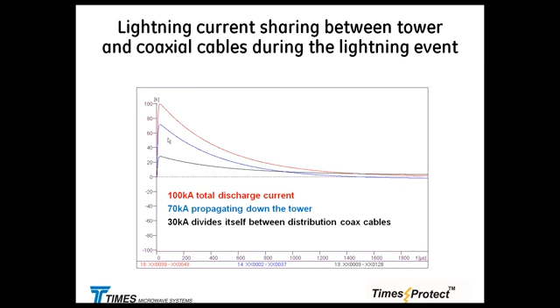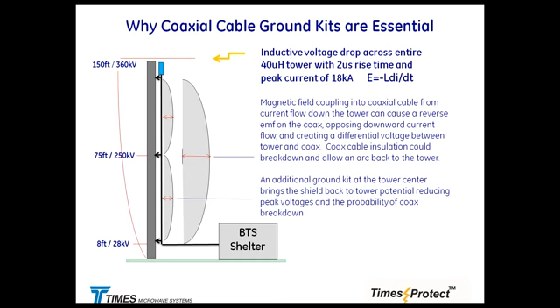People ask, why do we have to take a perfectly good coax cable, strip the insulation, apply the grounding kit, and tie it to the tower? The reason is the differential inductive voltage drop between the tower, due to its inductance, and the coaxial cable. We don't want to burn insulation, and we don't want to arc from cable to cable, or from cable to tower or cable tray. So the reason we are butchering perfectly good coaxial cables is to bring the inductive voltage drop across the tower closer to the inductive voltage drop across the cable. The rule of thumb is to do them every 75 feet. Many people follow this format, many do not.